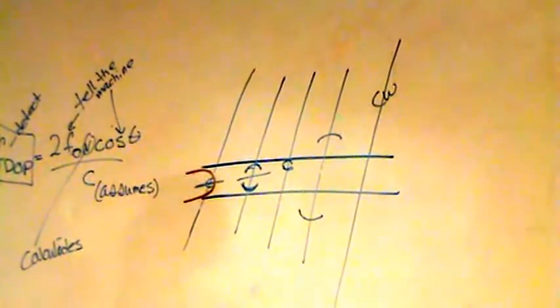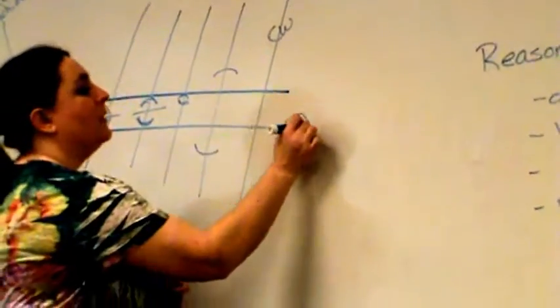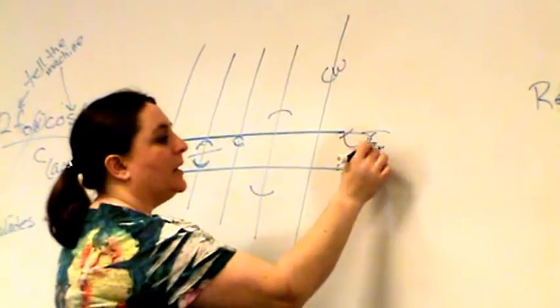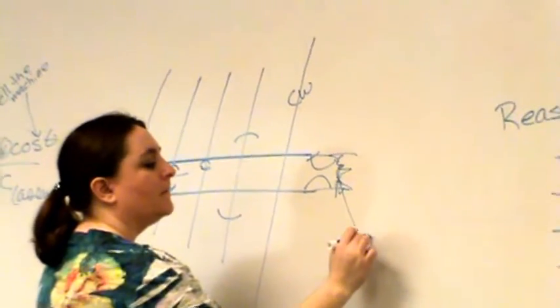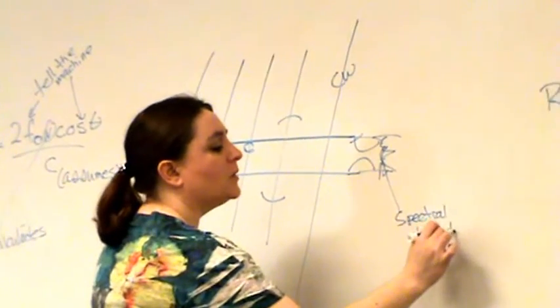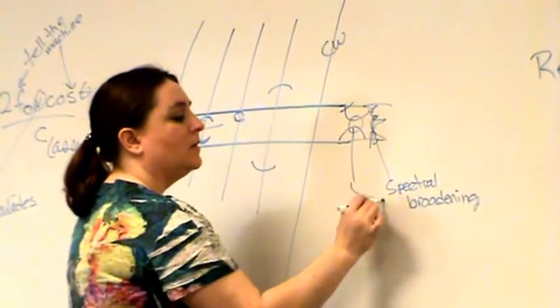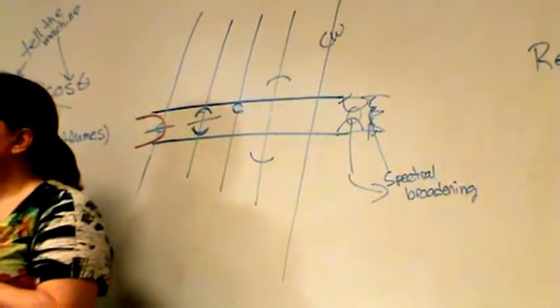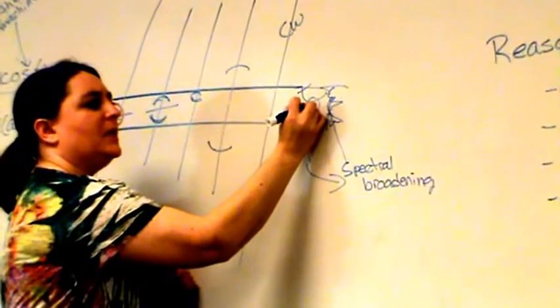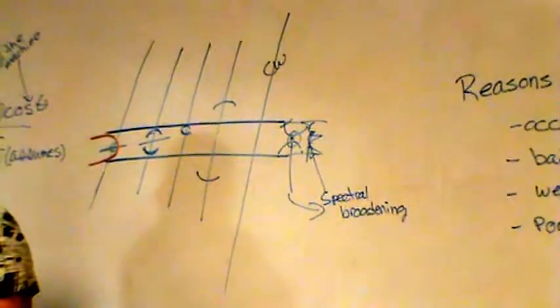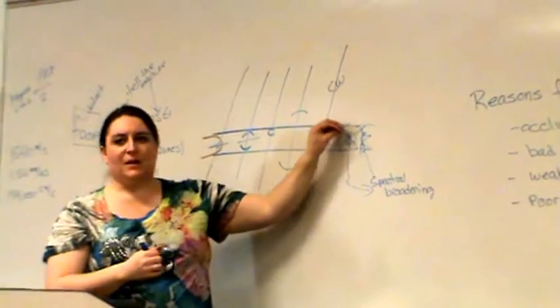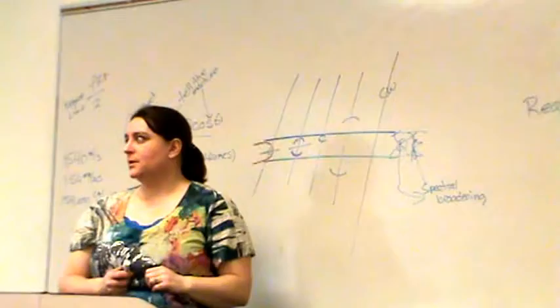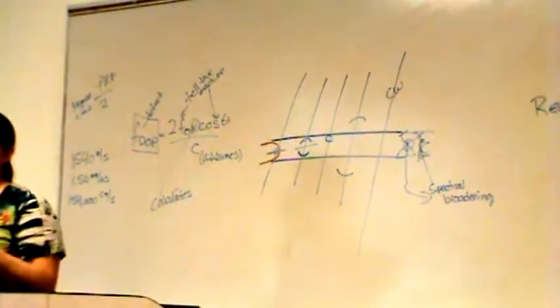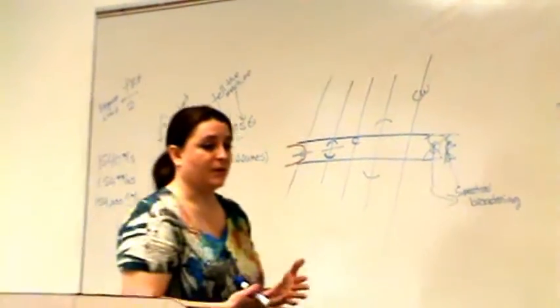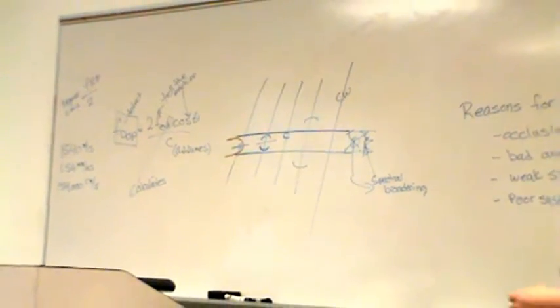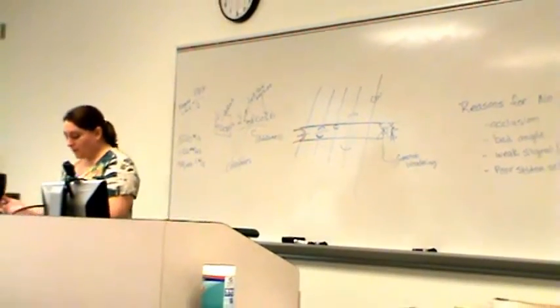And then the last reason I would have spectral broadening is if there was actually turbulence present. So if I have a stenosis and I have the turbulence out here, I'm going to detect the spectral broadening here in the turbulence, but I also will likely have spectral broadening even here in the stenosis, because if you think about it, can I get my sample volume small enough to be in the middle of this? And usually flow inside a stenosis isn't parabolic anymore anyway, it becomes more plug. But I'm not going to be able to get a sample volume small enough to just get center flow inside a stenosis. So that's typically why we end up with spectral broadening in a stenosis as well. We have not only some disturbed flow going on and multiple velocities, but we end up with a sample volume that we can't get small enough.